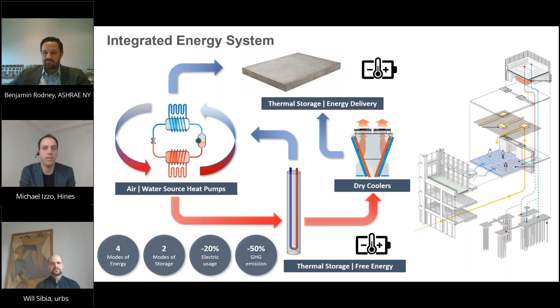Dropping the temperature in this heavy concrete structure by 2 degrees is a massive amount of energy, yet it has very little effect on the thermal comfort of the building. All told, by electrifying the building we've reduced our electrical consumption compared to a typical boiler, cooling tower, and chiller system by 20%. Right now we're projecting we're 50% below the 2030 targets set for New York, which are quite stringent, and about 80% of buildings in New York will be facing fines as a result.